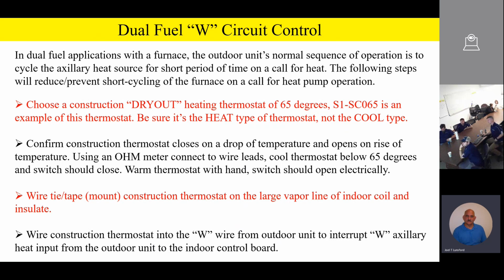And so you can confirm the construction thermostat closes on a drop of temperature and opens on a rise of temperature by doing the following. You can take your ohm meter and hook it up to the wire leads, and then cool that thermostat down below 65 degrees. Just put it in the refrigerator, or take just a glass of ice. You don't have to have water in it. Just stick it in a glass of ice, just some ice cubes, and cool it down, and click. The switch should close electrically. You can just look at it with your ohm meter.